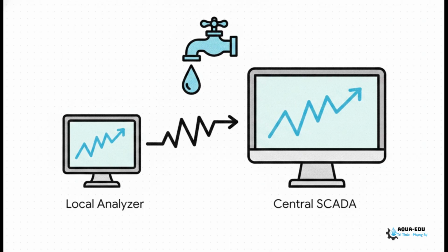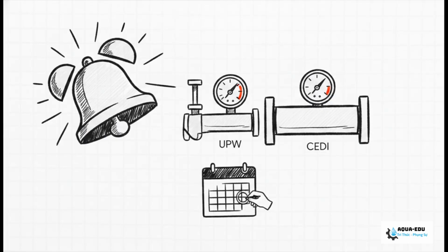Now, check your local LCD screen against your central SCADA monitor. If your local screen is reading 4.2 ppb, your central control room has to perfectly match that 4.2 ppb reading through the 4 to 20 milliamp or digital output. Brothers, do not forget to dial in these critical alarm set points before you walk away. A reading greater than 10 ppb needs to trigger the UPW loop alarm, and anything greater than 500 ppb triggers the CEDI feed alarm. Once that's set, update the calibration date in the system and schedule your next maintenance reminder for 1 to 3 months out.